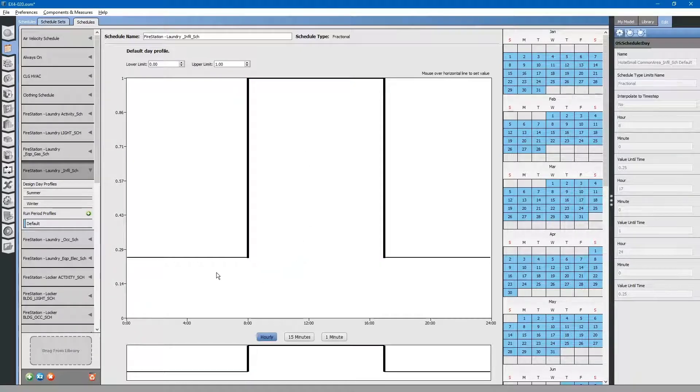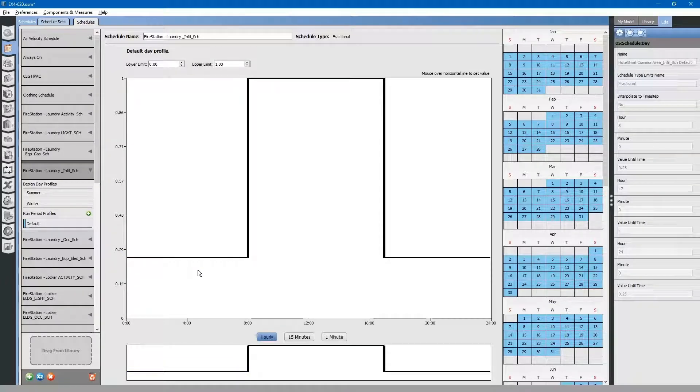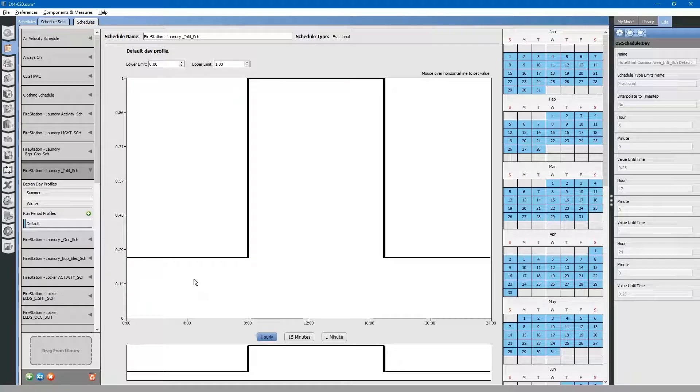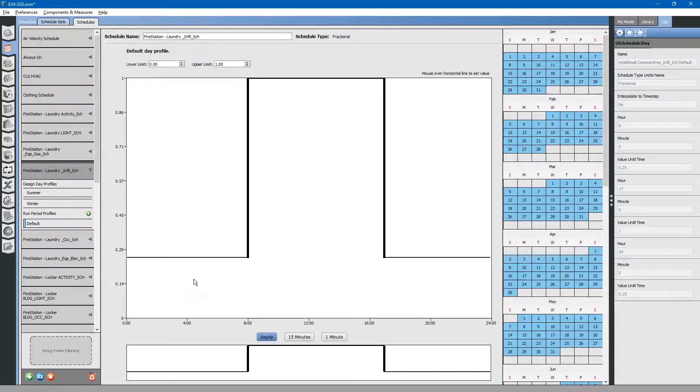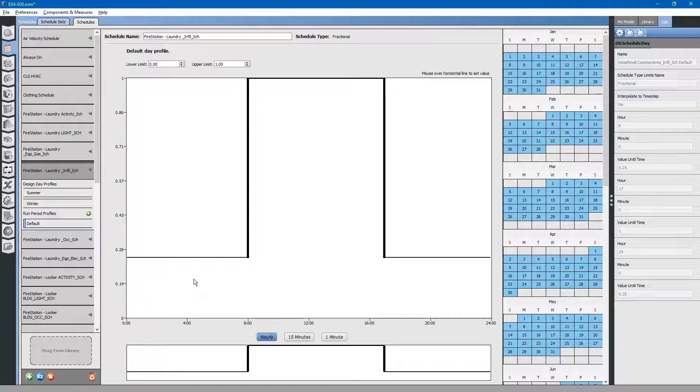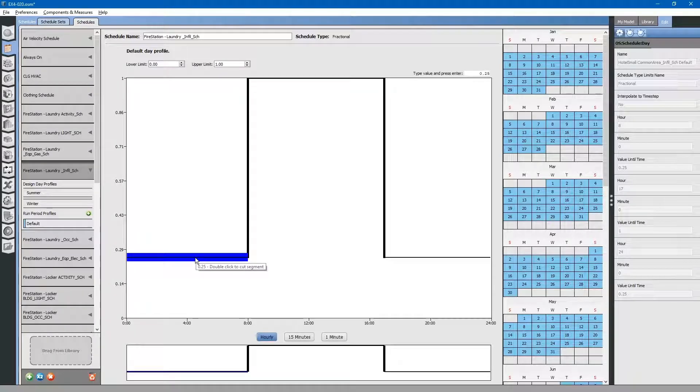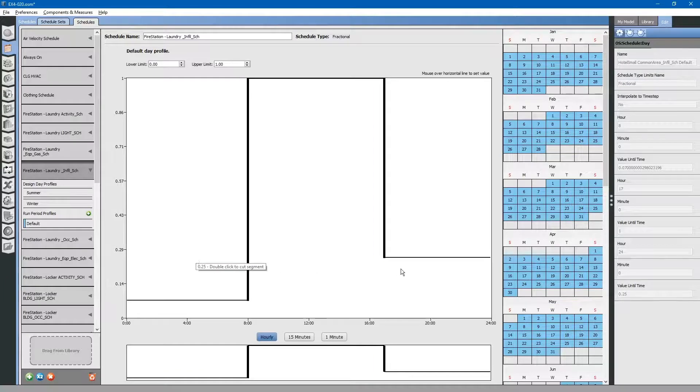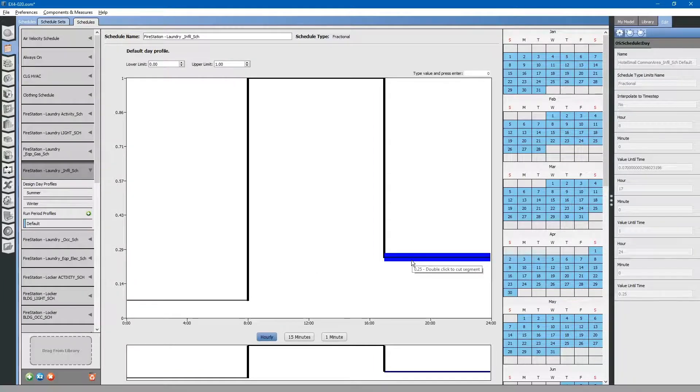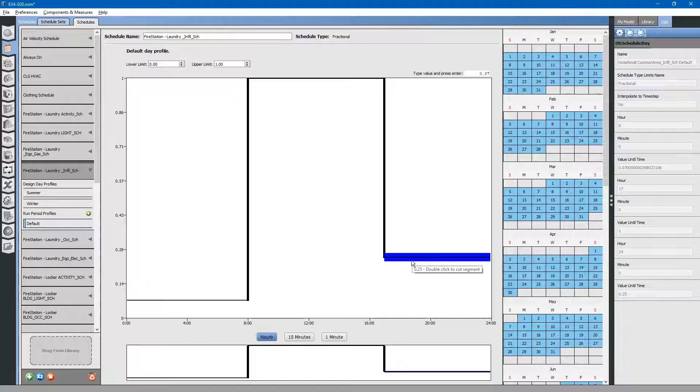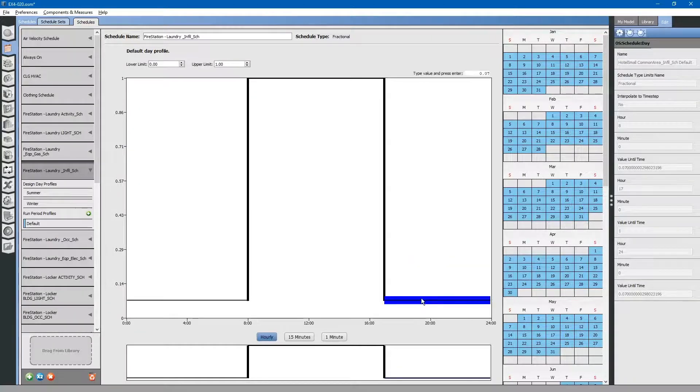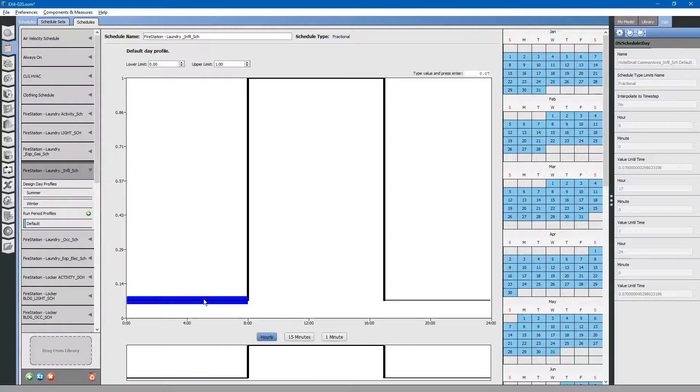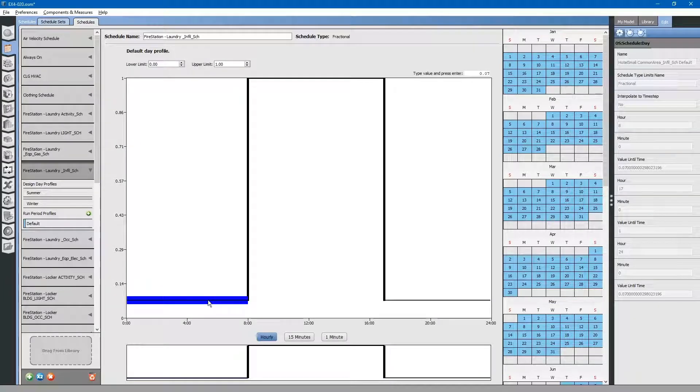In the evening, when that exhaust fan shuts off, it should go back down to the default, which we calculated as 10 CFM. That equates to approximately 7% of full air flow. We need to adjust those down for the nighttime hours just to reflect typical infiltration values.